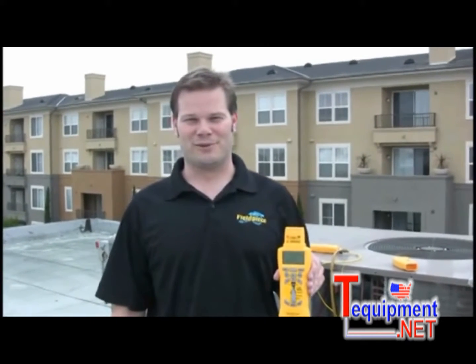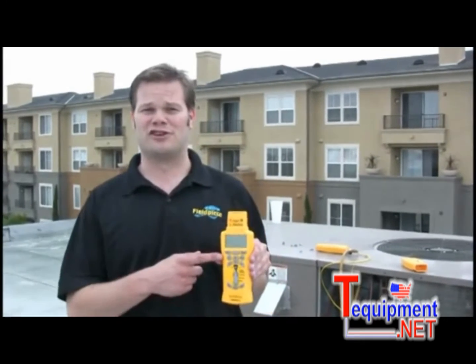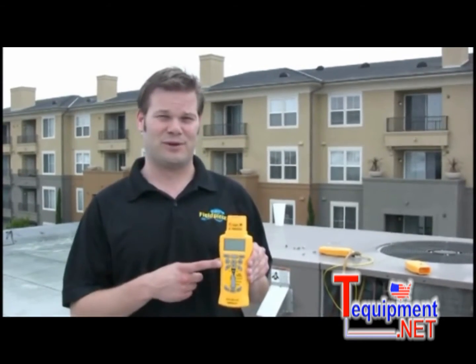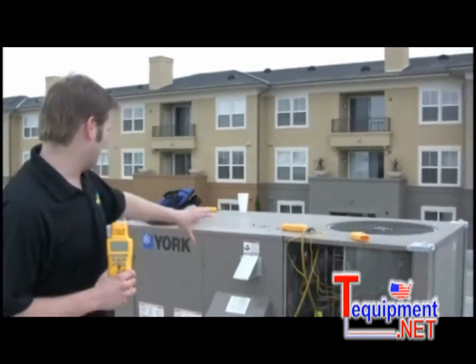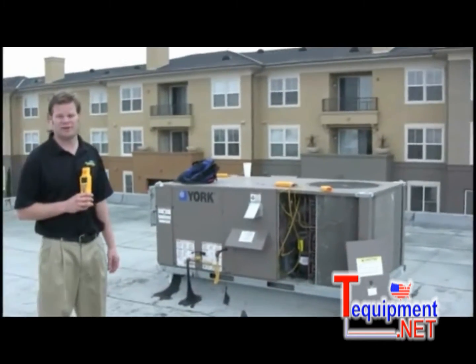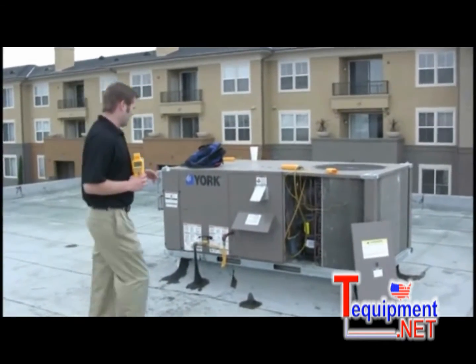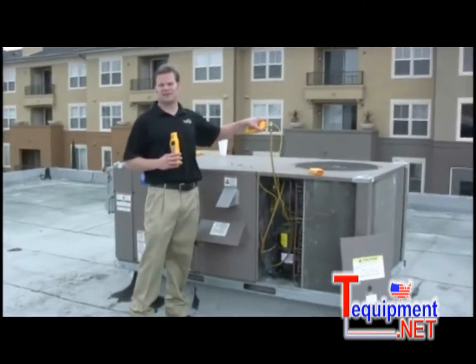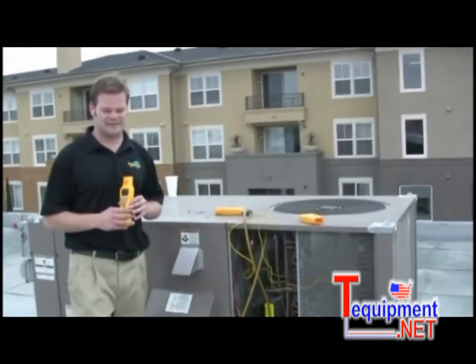Hi, this is Russ Hardy. We're on the top of Fieldpiece Instruments today, and I'm going to show you how to do a superheat test with the HVAC Guide. So behind me I have a package unit with R22. It's a fixed restrictor system. I have all of my sensors hooked up, they're ready to go, and they're ready to do a superheat test.